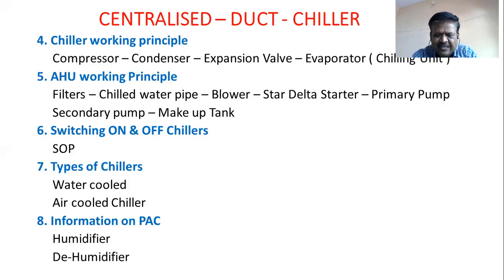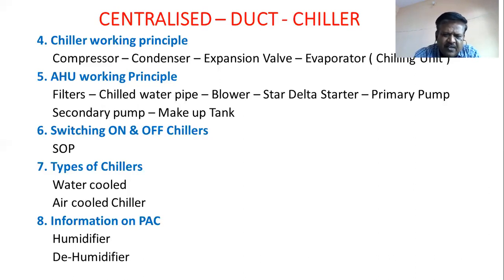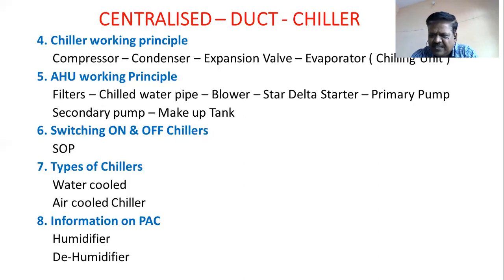For the switching off process: first switch off the chiller, then let the primary and secondary pumps run for half an hour — because the chilled water which is below 9 degrees centigrade will continue to circulate and maintain the cooling effect for 30 to 45 minutes. After completing all your daily work, updating all the records, then switch off the primary and secondary pump and then switch off the system.